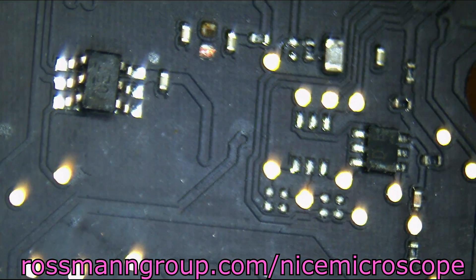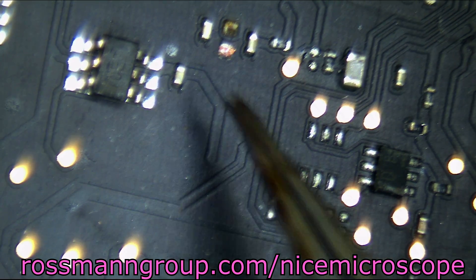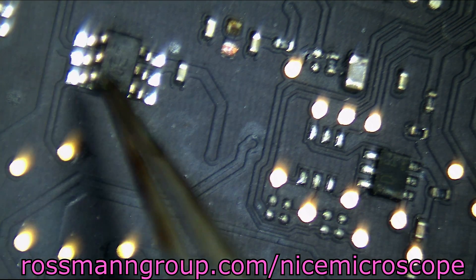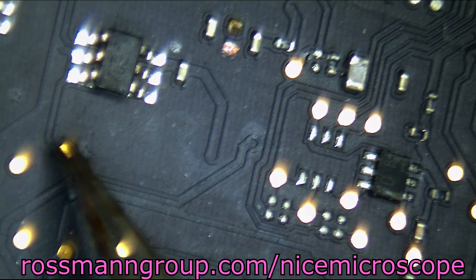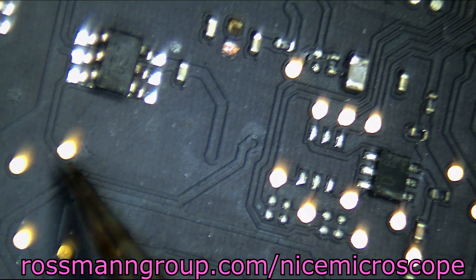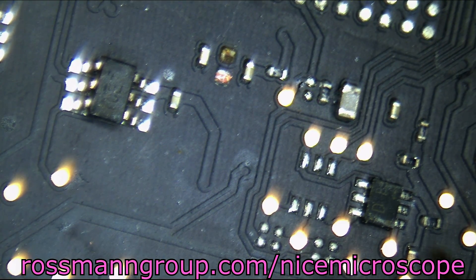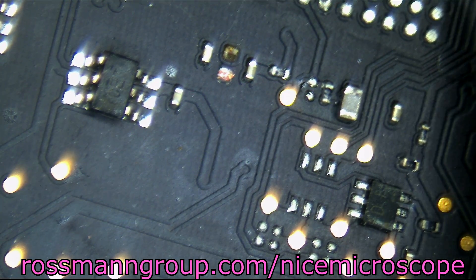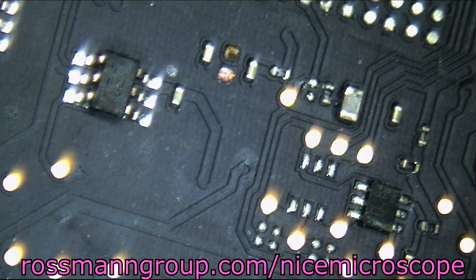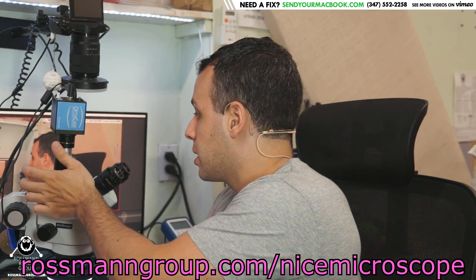Even when I get this into focus, you'll notice a couple of things that are different. You can see how the probe points have light passing off of them with a blurry effect on the lighting — the light is shooting off rather than just reflecting. And it doesn't necessarily have everything in the outer section in focus. I got the text in focus, but the stuff on the absolute edges is not in focus. Overall, even though the image through the eyepieces looks the same, the image quality in the trinocular port is considerably less when using this piece.